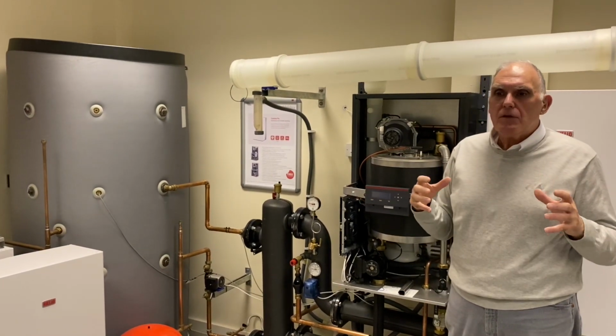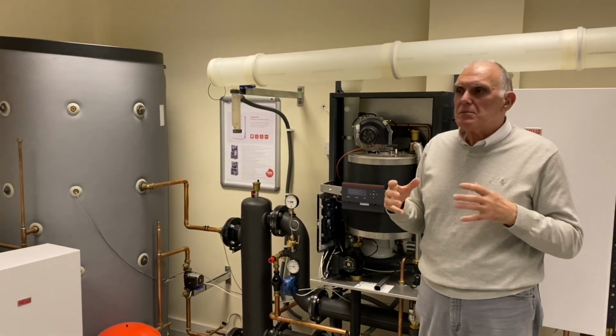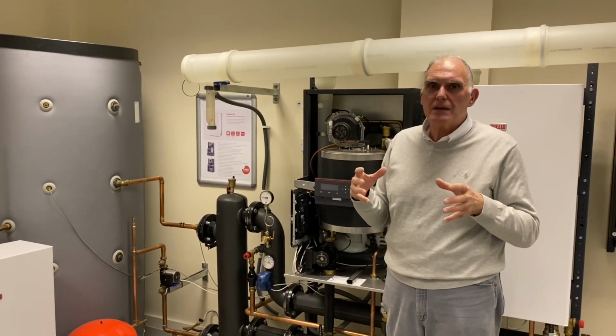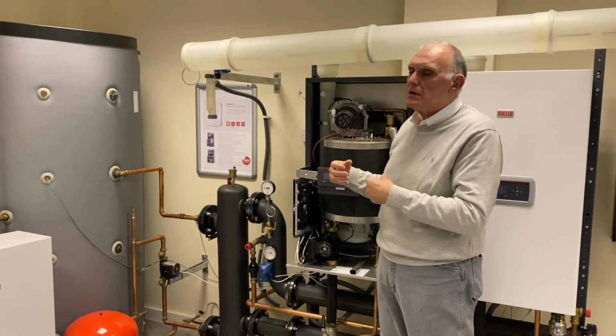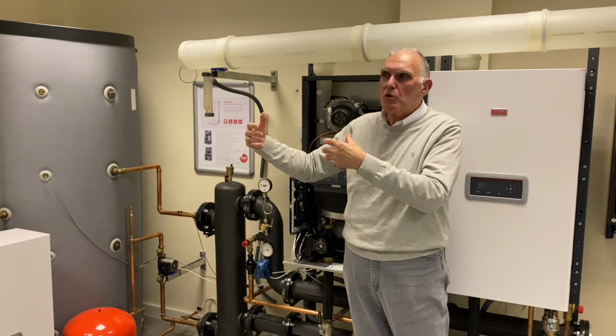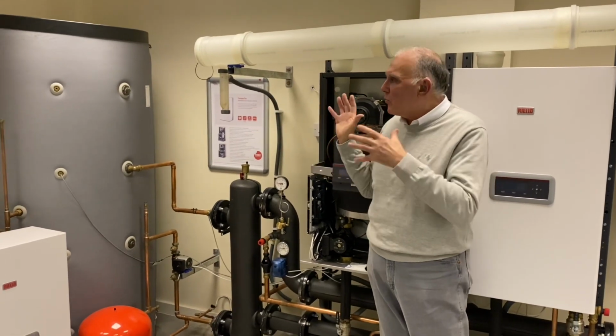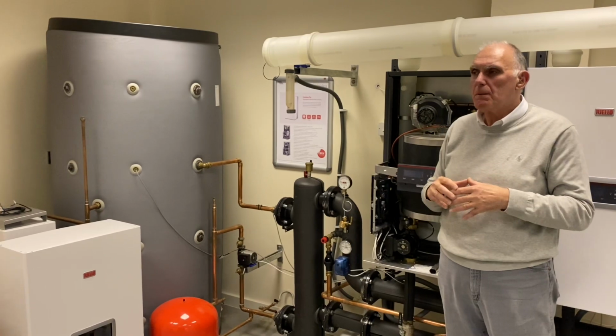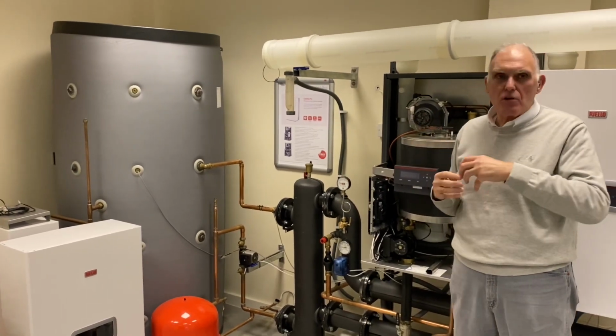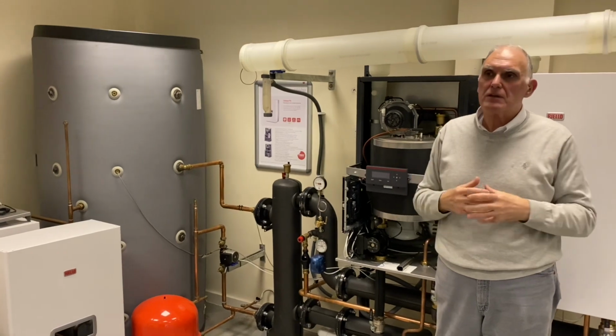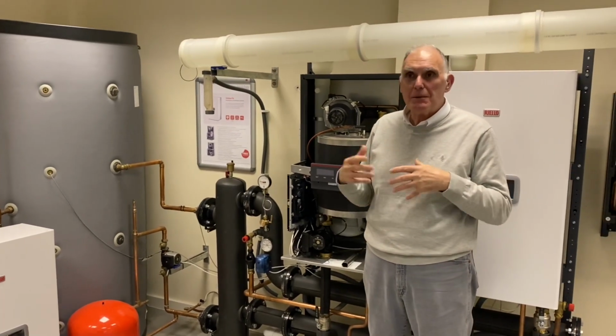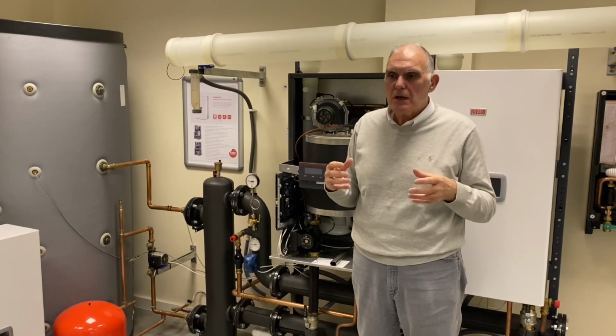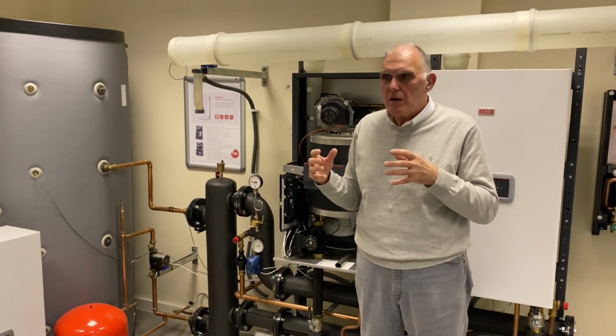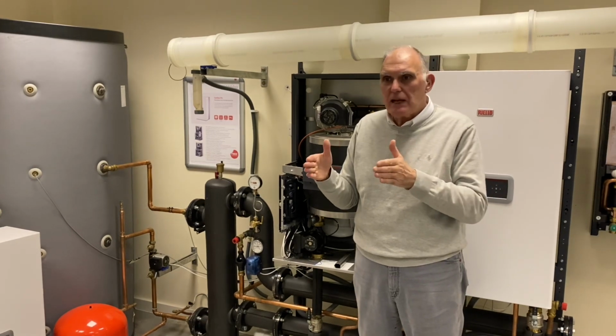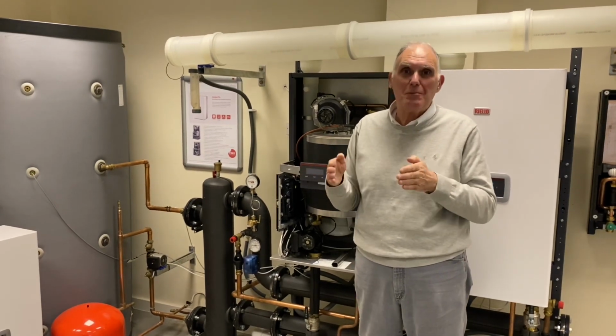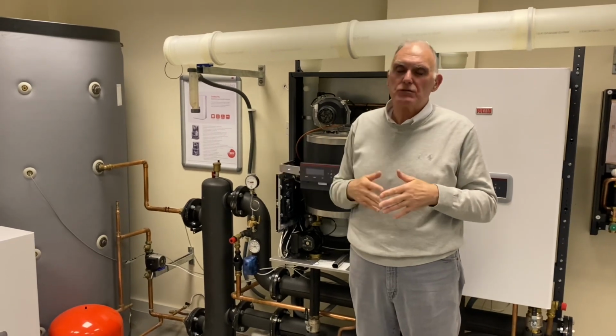And of course, for some developers, that gives them the opportunity to have more than one source of heat. So you could have gas boilers, a solid fuel boiler, an oil boiler, solar panels, all putting heat into a thermal store, and from that thermal store, the primary flow and returns or communal flow and returns would be distributed around the building, and it becomes easier for developers to manage the energy supplier and choose an energy supplier that's giving you the best deal at the moment, whether it be oil, LPG, natural gas, whatever.